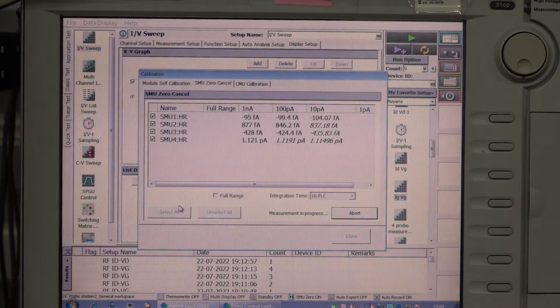So I select basically all and I give continue. The device under test has to be removed so that the instrument can calibrate. Now the instrument is calibrated, we can see there is no error here. Earlier we had some error. The error could be the setup error, and there could be some stress in the cables, or the cable is having high leakage. Those cable leakage and contact resistance leakage are all taken care of with the measurement setup. Once we calibrate, these measurement values are taken into account of the noise level. So now my calibration is done.